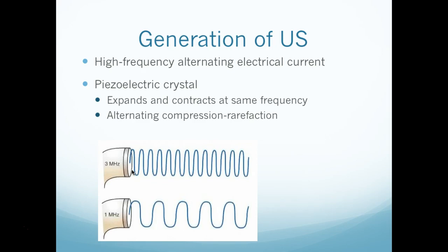They have improved that quite a bit. You still want to be careful and have good contact, but you're not going to be as concerned about it destroying that sound head, and they have a little beep system if you aren't on contact to kind of let you know where you're at. So basically what happens with that is you get this expansion and this contraction at the same frequency, and you have that alternating compression rarefaction we talked about that creates that wave.